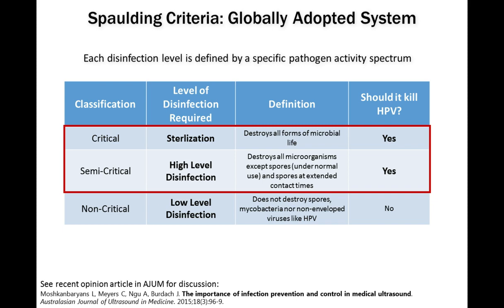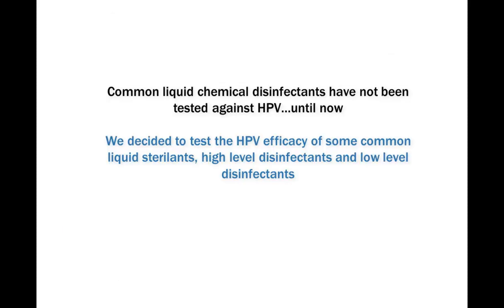If you look at the classification for semi-critical, and this is a key area of our discussion today, this is classified as high-level disinfection. The definition for this is that it destroys all microorganisms except spores under normal use, and that it will kill spores at extended contact times. So according to this definition, it should be able to kill HPV. So if you're using high-level disinfection, according to the definition, HPV should be deactivated or killed after processing under this classification.